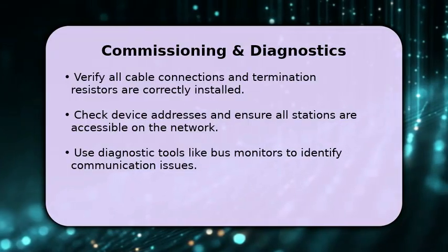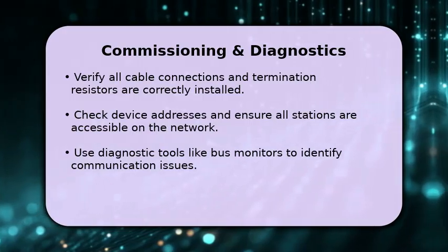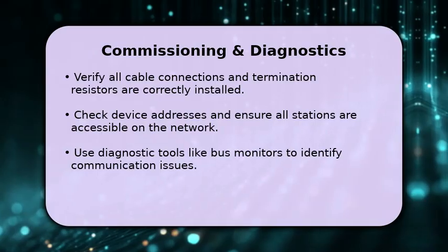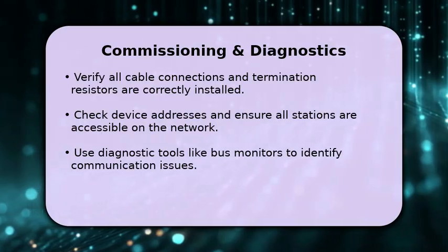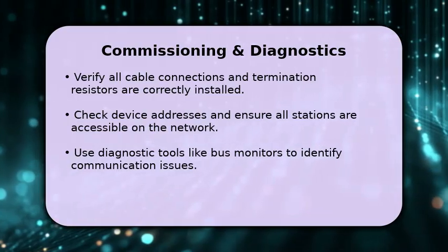Begin by visually inspecting all cable connections and confirming that termination resistors are correctly engaged at both ends of each segment. Verify that every device has a unique address and is accessible on the network.